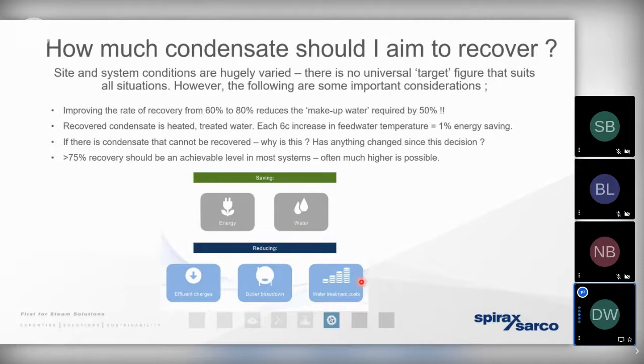But we need to be aware of what the benefits are of recovering as much condensate as we possibly can. In the example that you can see, by increasing the rate of condensate recovery from 60% to 80%, we've reduced the amount of makeup water that we could be consuming by 50%. So that's a significant cost saving on water alone. And we also know that if we can recover more and more of that condensate at a nice high temperature, 85 degrees or above, well, if we observe a rule of thumb that says every 6 degrees we can increase the temperature of the feed tank by, it's going to result in approximately 1% in fuel savings, in energy savings.